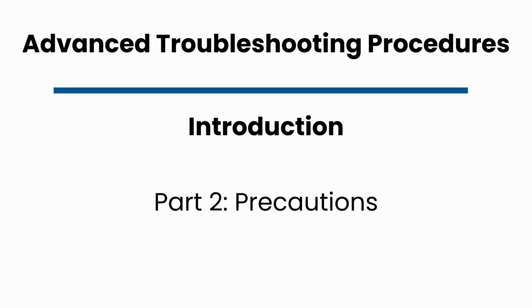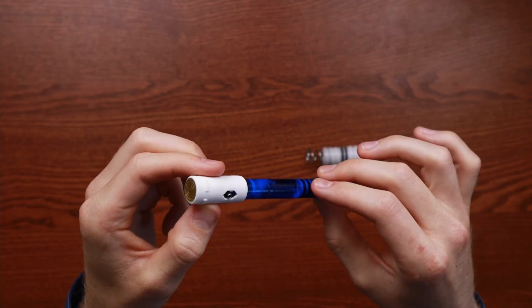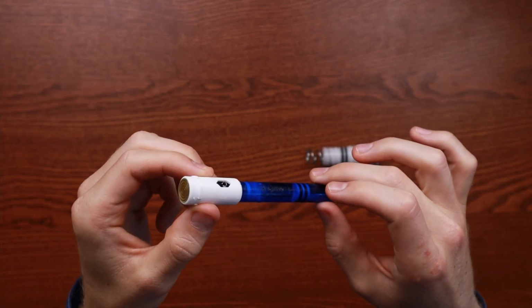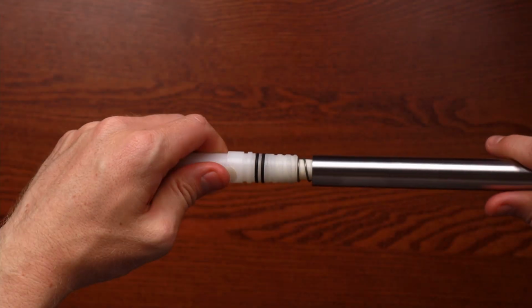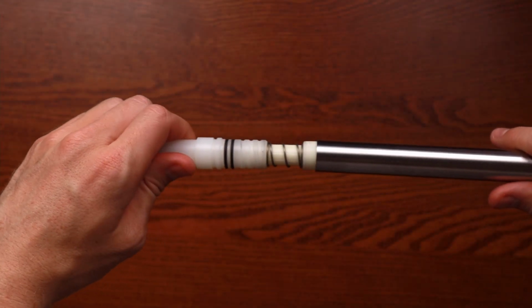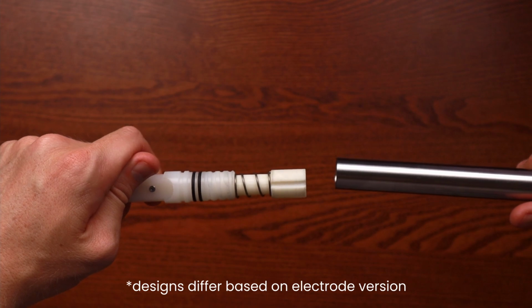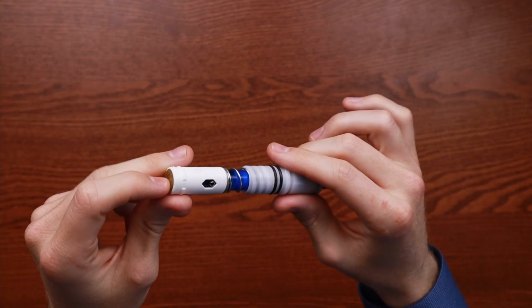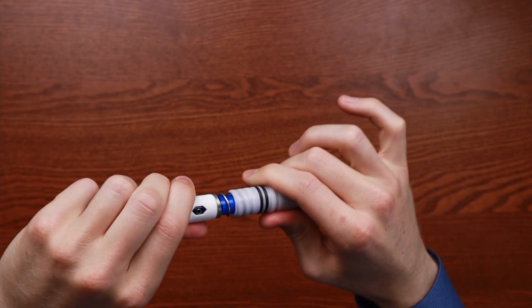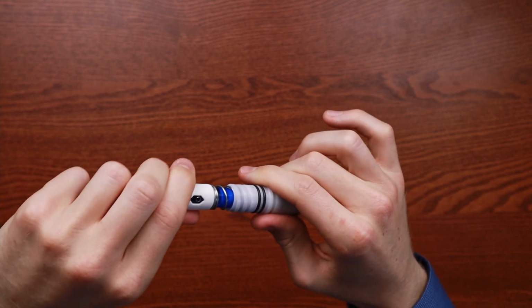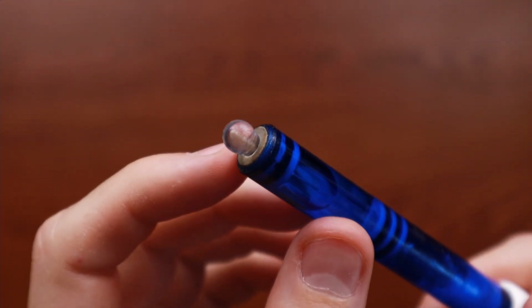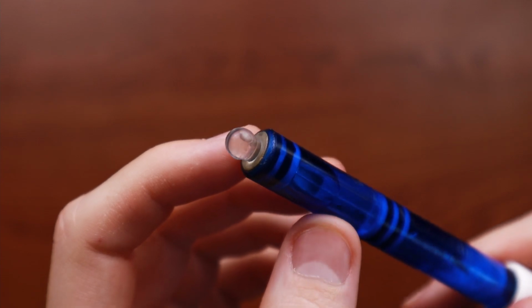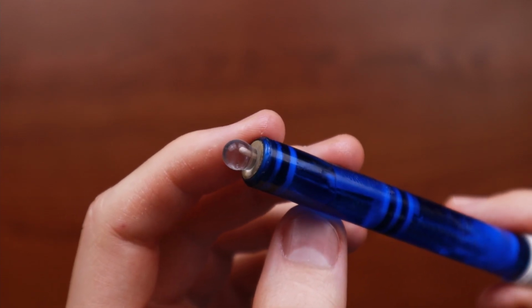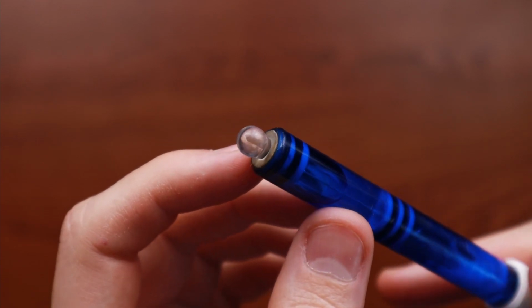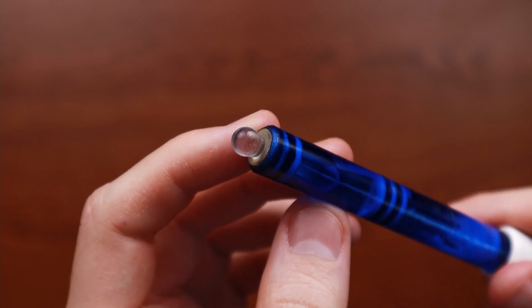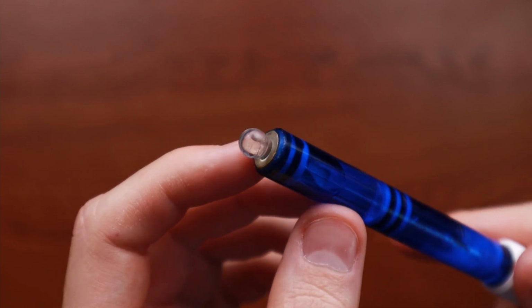On to precautions. Versions of the electrode cap have ridges that may catch on the dimple in the housing when trying to remove it. Gently twist while pulling to find the grooves that slide past the dimple. Whenever the electrode needs to be removed from the electrode body, avoid yanking on the cap because that may cause damage. The tips of pH, ORP, and dissolved oxygen electrodes are sensitive, so measurements can be affected by oil residue left from your hands or from small scratches. Always handle with care and put them in a place where they cannot roll away when working with them.